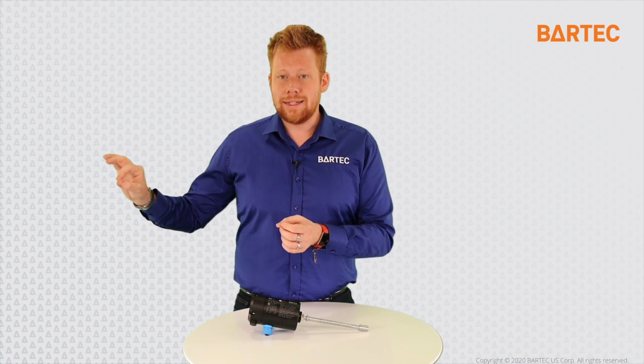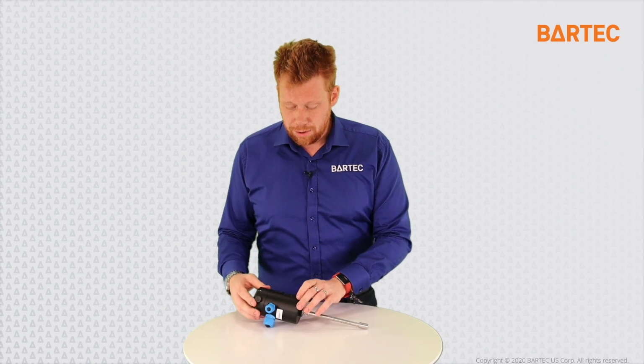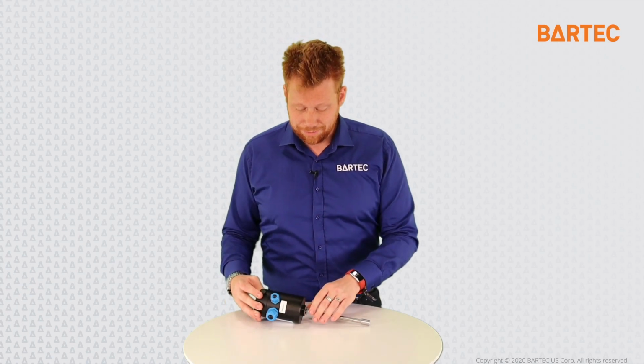So, as I said, there are various components that make the Hygrophil F analyzer. The first part is the evaluation unit, or the analyzer. This is where we have the light source. This is where we do all the mathematical calculation because of the processor in it. This is also where all the signal and communications with the DCS come from and arrive to. We then have a fiber optic. So the light source in the evaluation unit sends a light signal through the fiber optic all the way to the probe through this connector.